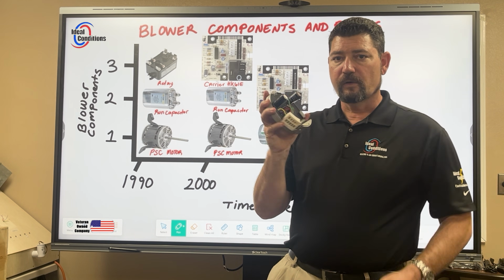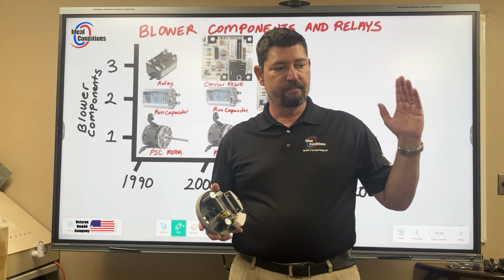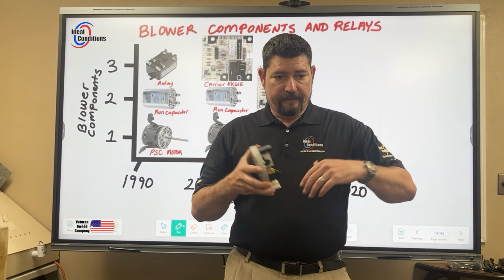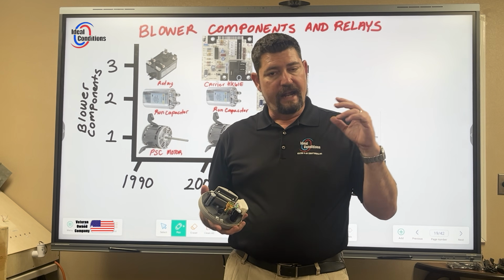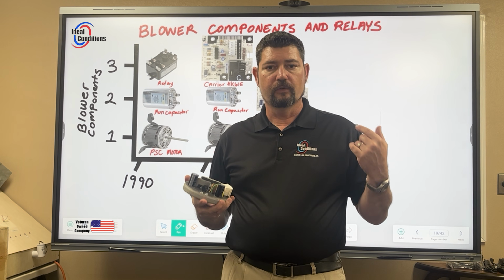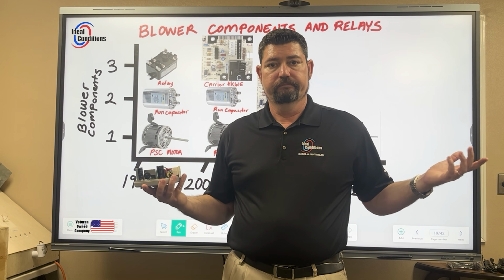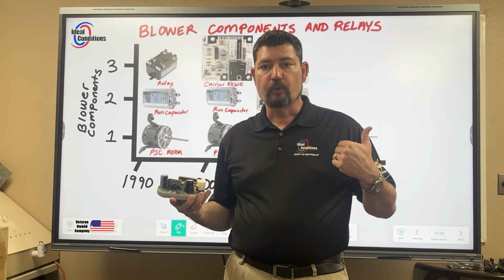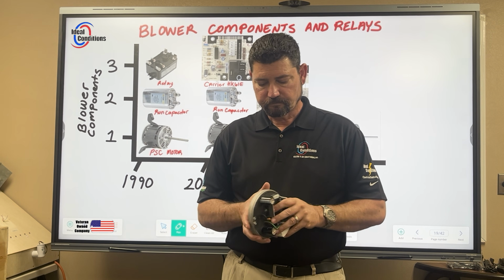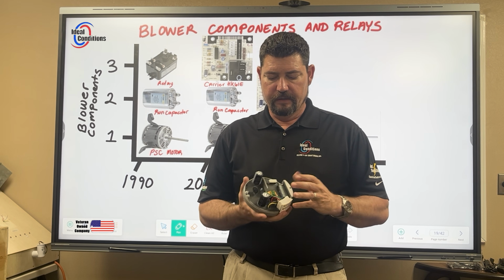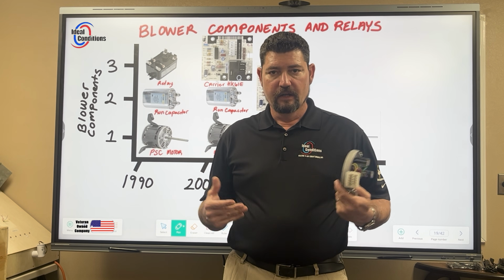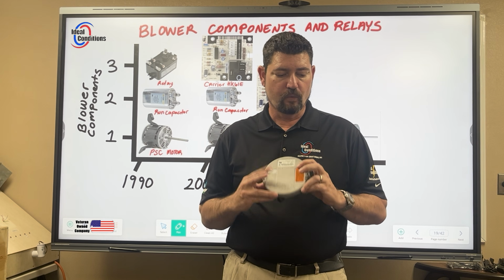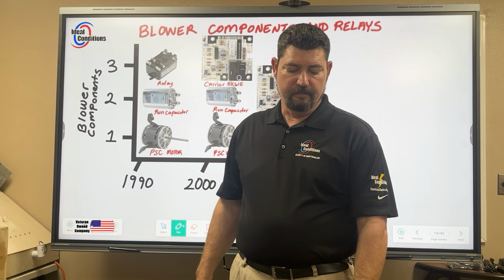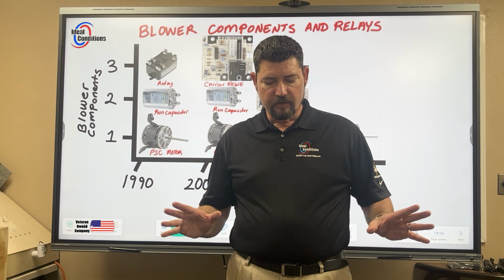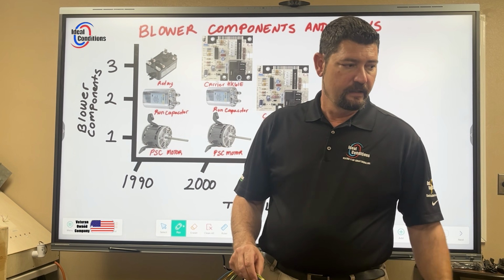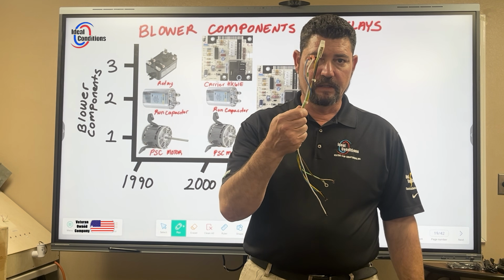Now, once we put power on this, 230 volts, it's like a capacitor. You put power on a capacitor, there's power on that capacitor that's stored. So you have to short those capacitors out so you don't get any of that voltage that's stored. You don't want to hurt yourself. All these capacitors that are in here are also storing that energy too. There's a warning label on there for your safety. And make sure there's no power on it, no high voltage. The best way to do that, pull it out of the cabinet or unplug it.